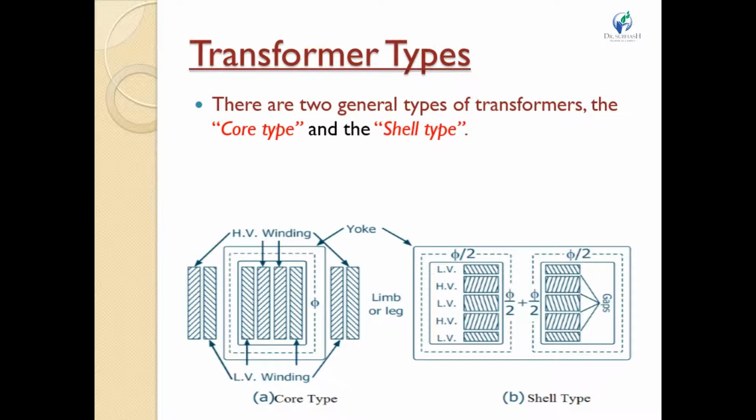With this arrangement of windings, only one layer of high voltage insulation is required, and removal or repair of the high voltage winding, which is more prone to fault than the low voltage winding, is easy and convenient.